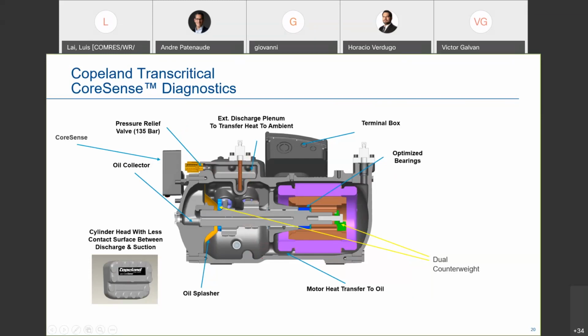Now, the oil collector I talked about, the sight glass is nice and high because this flinger, the yellow blade here, as this compressor is turning at 1750 RPM, is splashing oil up, falls into this collector, and the collector is allowing oil to get transferred through the compressor. So you can put an oil level regulator, electronic oil regulator, on either of the low oil sight glasses.